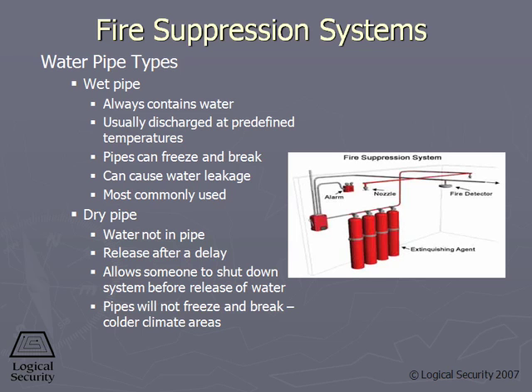Now, this does a couple things. First, we'd place the shutoff valve in a thermally stable area, so that the pipe that might be in a non-thermally controlled area does not contain water, and therefore, if it gets very, very cold, there's nothing inside to freeze, there's no expansion, and there's no breaking of the pipes.